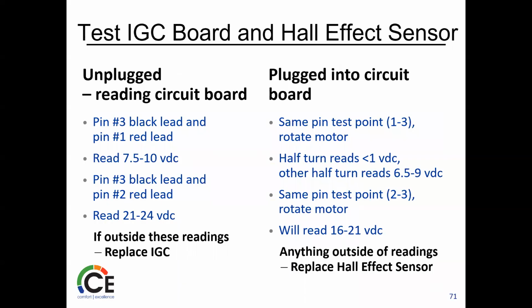They are pretty simple to test. You're really just looking for voltage, right? So between that black and red lead, we're looking for DC voltage. Between pins 3 and 2, which is another black and red lead, you're looking for 21 to 24 volts DC, 2 sides of the switch. Okay, that's the little rotor in there, turns around inside that device, and if it hits it fast enough, everything's fantastic. So we're looking for that first. If you have that, then your issue is most likely in your control board. If you don't, then we're looking somewhere else, right?